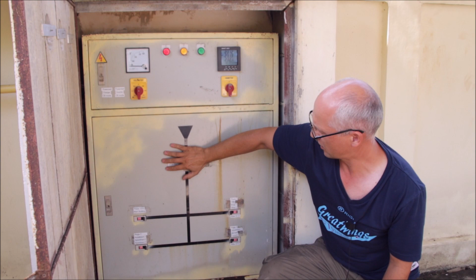So up to the main breaker, that's what the regulator wants to see is correct. Everything beyond the main breaker - here I have four main circuits which are further distributed as a TNC initially inside the property, and then you have a TNCS earthing system from every building onwards. That's actually it - they're not interested in how safe you are, whatever you do.